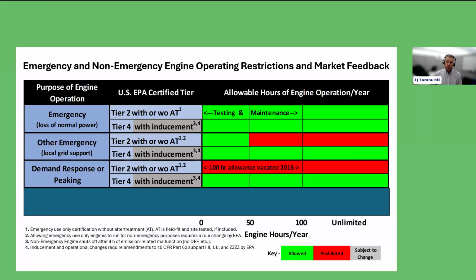Historically, the EPA rule allowed up to 100 hours of operation for peaking and demand response, but this allowance was vacated by court decision in 2016. Consequently, when you look at this Tier 2 engine with or without after treatment, it is not allowed to operate at all for those purposes under the current regulations.